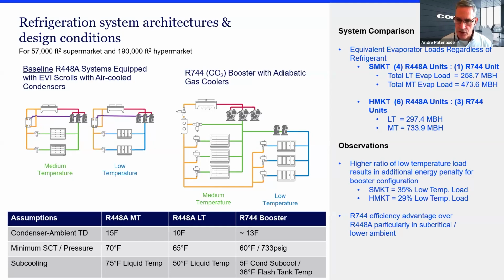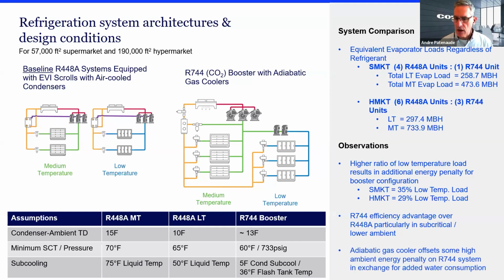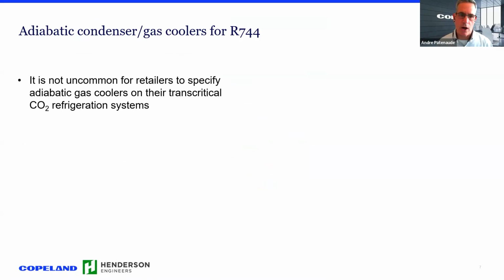And then the last observation here that we've listed out talks about the adiabatic gas cooling, which I already mentioned, provides high ambient mitigation, so energy efficiency gains versus a dry gas cooler. And that changes dramatically based on how dry your regions are. But that was part of our study. So the next slide talks about adiabatic gas cooler and really how much moisture, how much water we're using. We know that they are common, so that's why we chose them.